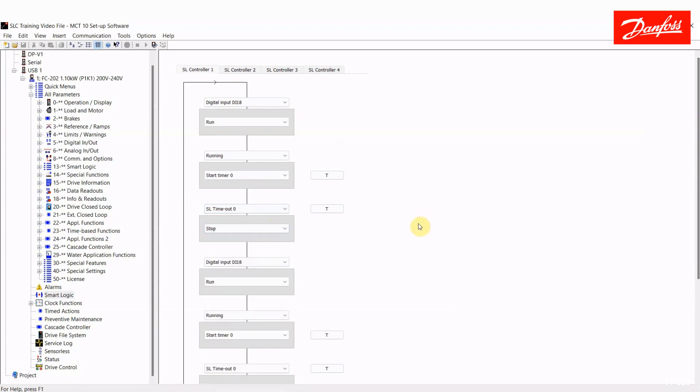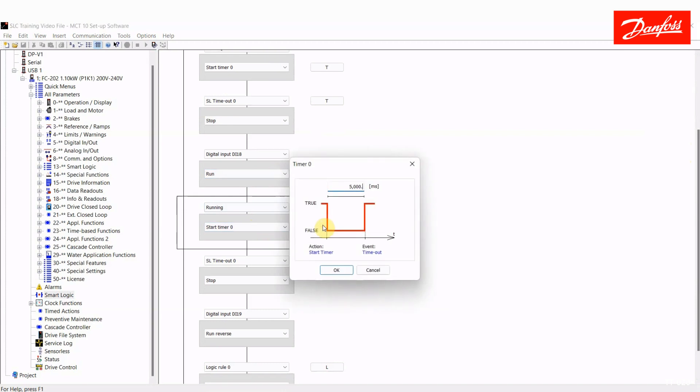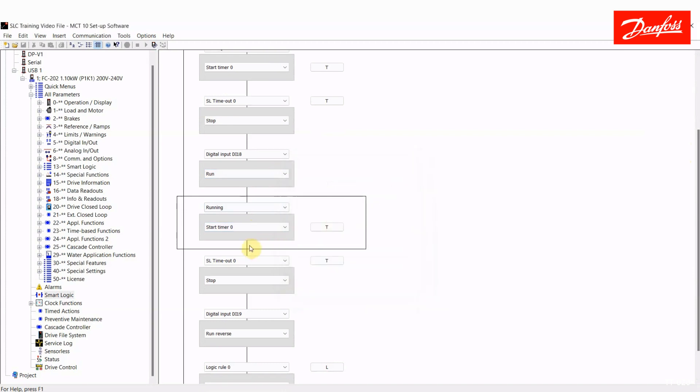Now, at this point, nothing will happen until someone presses the same button again, digital input 18, and I've repeated this sequence. The drive will run. When it's running, which is true, I'll start that same timer, which was my 5 second timer. When the 5 second timer expires, the drive will stop. At this point, the vent will be fully open.